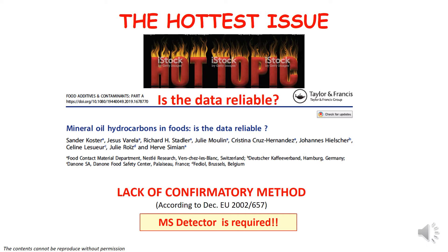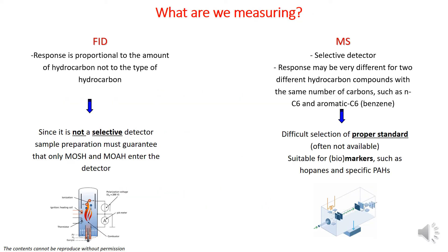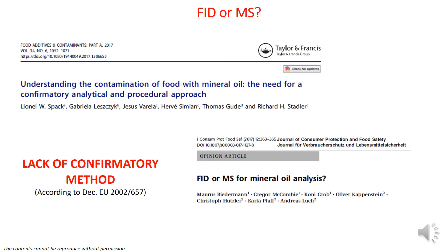One of the hottest topics in MOSH/MOAH determination is the lack of a confirmatory method involving an MS detector, as required by European Decision 2002/657. For quantitative purposes we use FID, which gives virtually the same response factor regardless of the hydrocarbon type. However, FID is not selective, so we must guarantee that only MOSH/MOAH enters the detector. MS gives us the desired selectivity, but the response factor varies with different hydrocarbons and a proper calibration standard is not available — so the question of whether to use FID or MS remains an important debate.